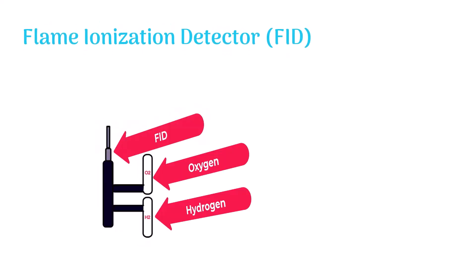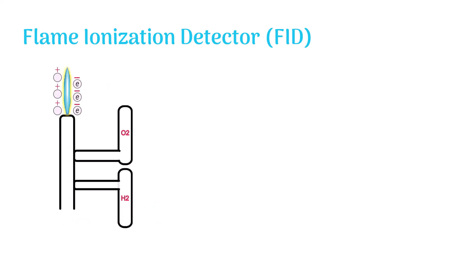The flame ionization detector, FID, has access to hydrogen and oxygen, which it uses to produce a flame. When sample molecules pass through it, they are ignited in the flame and made ionized. The flame is surrounded by electrodes.